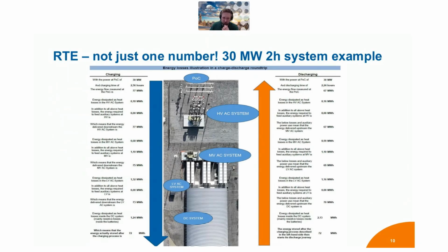Here you can also see that the biggest losses happen inside of the battery, and it is quite counterintuitive when you charge or discharge the battery energy storage. If you measure the energy flow from the DC terminals of the battery when you're charging it and discharging it, the value is not the same because you always lose some energy with the internal heat losses. When you are charging a battery, you can think of a bucket which you are filling with water that has a hole in the bottom. You measure how much water you are pouring into this bucket, and some goes through the hole. Then you stop pouring water in there, and you close the hole, and then you notice that the water you put in is not the same as what you measure that is inside later on when you pour it out of there.